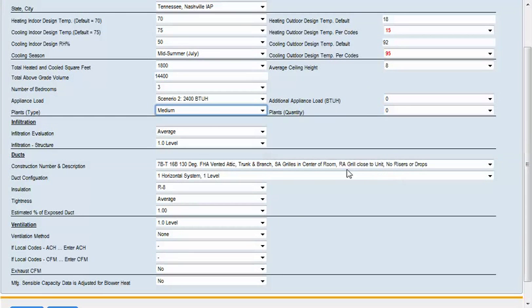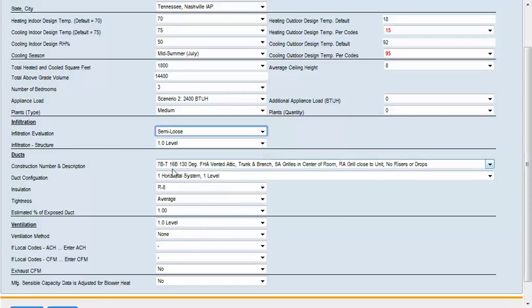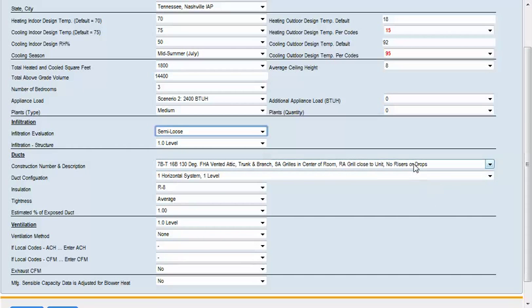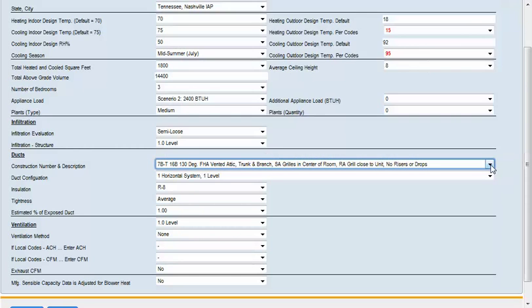This is an older home so I'm going to change the infiltration evaluation to semi-loose. It is a one level home. Our ductwork is located in the attic. It's a 130 degree attic, FHA vented, trunk and branch, supply grills in the center and the return grill close to the unit with no rises or drops. By selecting the drop-down you can select any other duct table that you might find in the book. The duct system configuration is one horizontal system on one level.